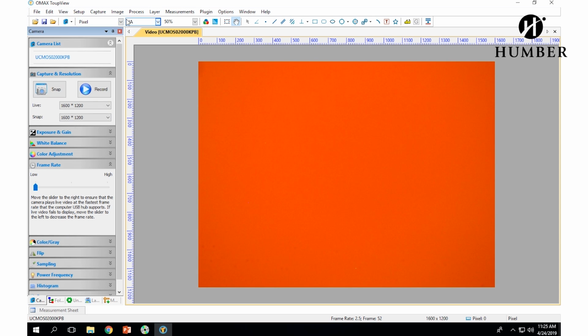When we go on to the top bar, you don't want it in pixels, you're going to click millimeter. We're going to measure our cells or whatever you're measuring in millimeters. So in this process of calibration, we need to select millimeters because of the stage micrometer, which is also 1 millimeter. And then you're going to make this 100%.